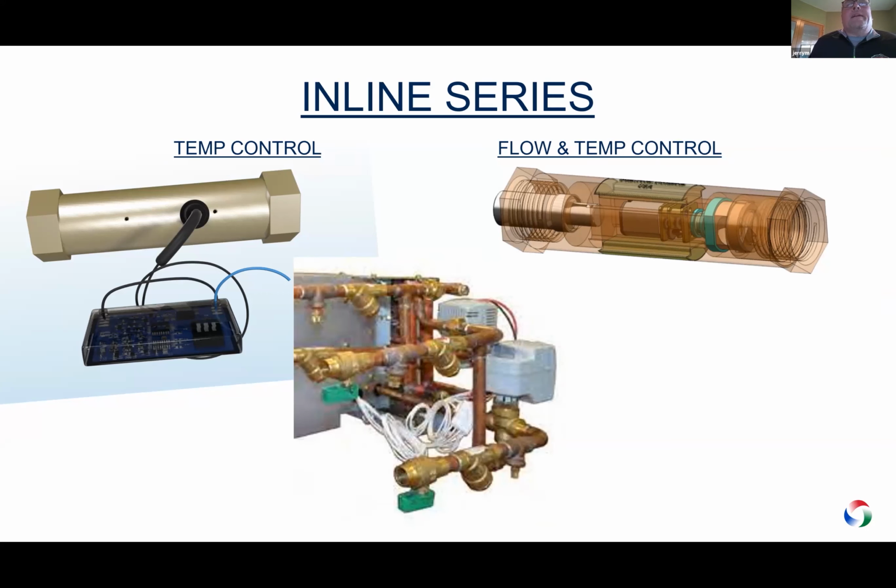I'm going to say cutting edge technology. There's no ball inside of this valve. We're using a ceramic disc to give us the characterization we want so that we can get a good equal percentage characteristic. So this is the new and latest and greatest coming out of Griswold Controls. I really appreciate your guys' time.